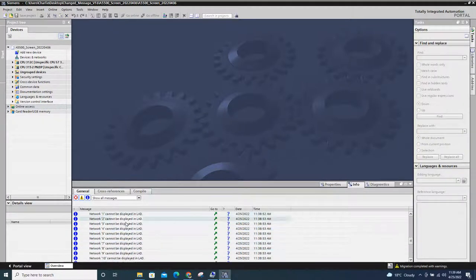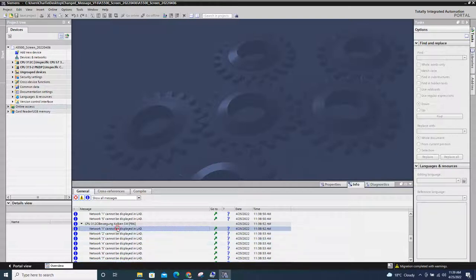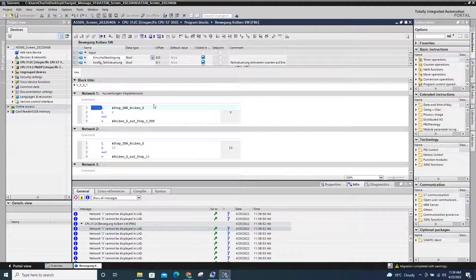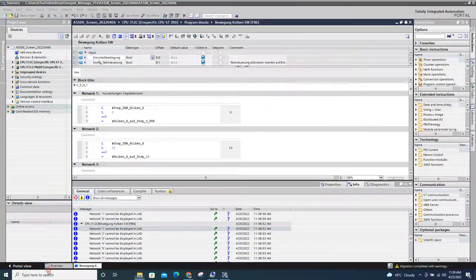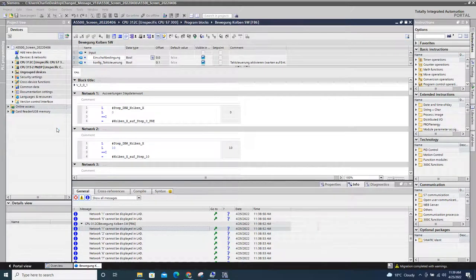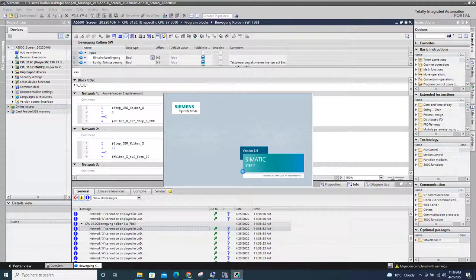Let's do a quick comparison between the original SIMATIC Manager project and the TIA migrated version to see if the networks are the same. When migrating, if a ladder element is not recognized by TIA, it will be converted directly to STL. If I click on this error, network one is now in STL in the TIA version.